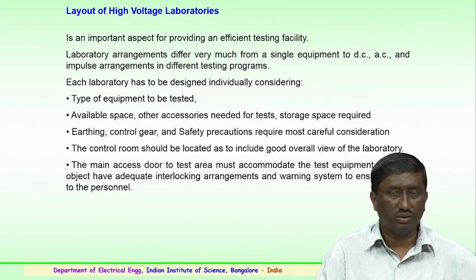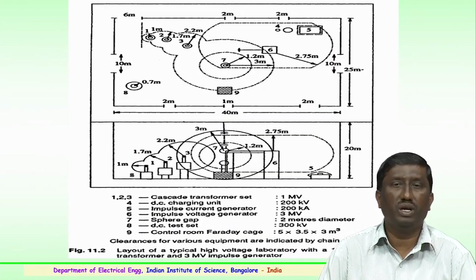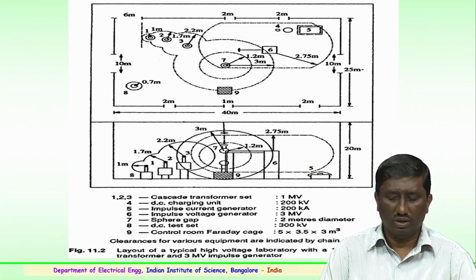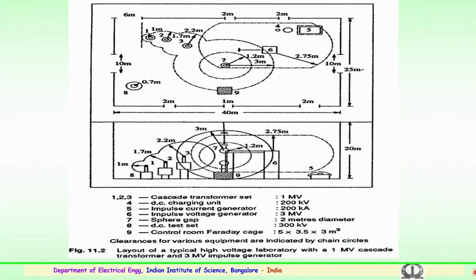important factors. So, this is the typical layout of the high voltage laboratory with a 1 million volt cascade transformer and a 3 million volt impulse generator. This is just to show how the clearances of various equipment are to be considered. You can see that this 1, 2, 3 here, these are the cascade transformers, each of a particular rating of 350 kV. Say it is a 1 million volt source. The minimum clearances are indicated here, 1.7 and 2.2 meters are the minimum clearances which are essential to be kept away. Then you have a DC charging equipment, which is very important.